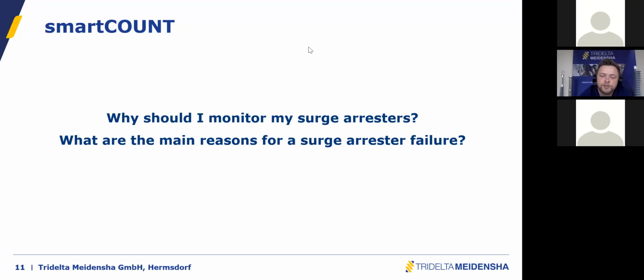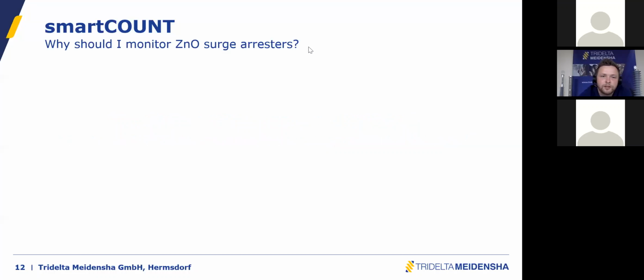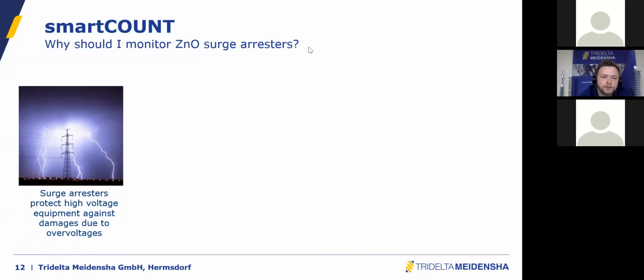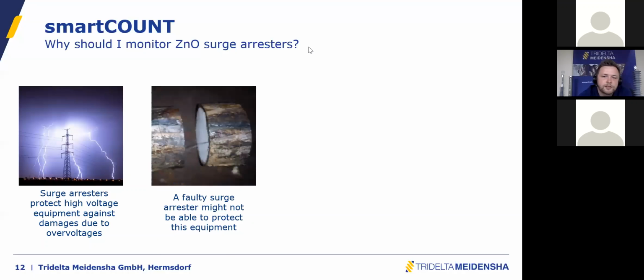So I would like to put some light on those two questions. Let's begin with, why should I monitor surge arresters? The argumentation chain is very easy. So you have surge arresters in your grid, and they are protecting your primary equipment against damages due to overvoltages. If there is maybe 1 out of 1,000 or 1 out of 10,000 surge arresters, let's say a black sheep among all the surge arresters which are normally highly reliable, there might be one that is damaged, maybe because of some duty it was not designed for, maybe a high discharge current, maybe a mistake in the manufacturing.